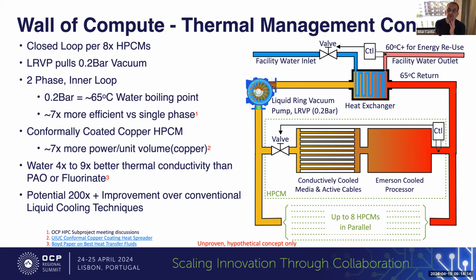So we do need a control loop on this vacuum pump to see that we're pulling 0.2 bar for the 60 or 65 degrees C, whatever that is. I was going to put a sensor on the vacuum on this side to control the speed of the vacuum pump, I guess. Where's the sensor? I don't have it in this diagram yet, but I have to put one in for that.